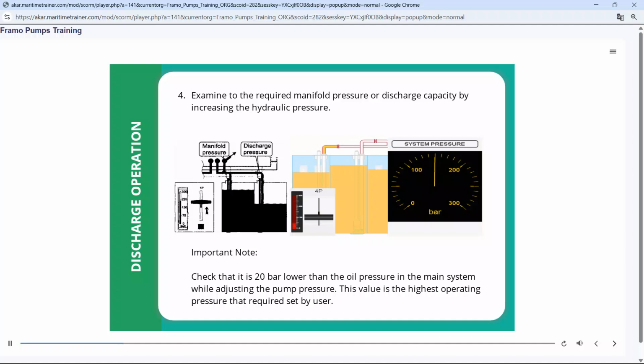Reach the required manifold pressure or discharge capacity by increasing the hydraulic pressure. Important note. Check that it is 20 bar lower than the oil pressure in the main system while adjusting the pump pressure. This value is the highest operating pressure required, set by the user.